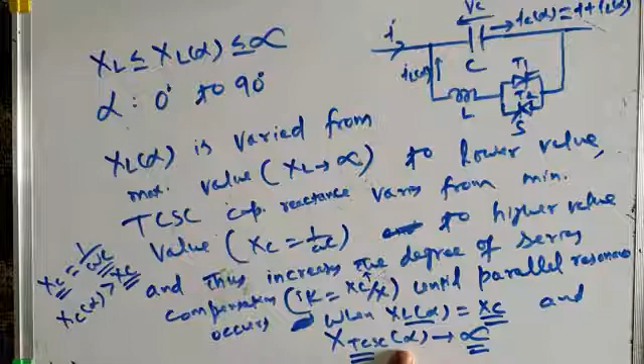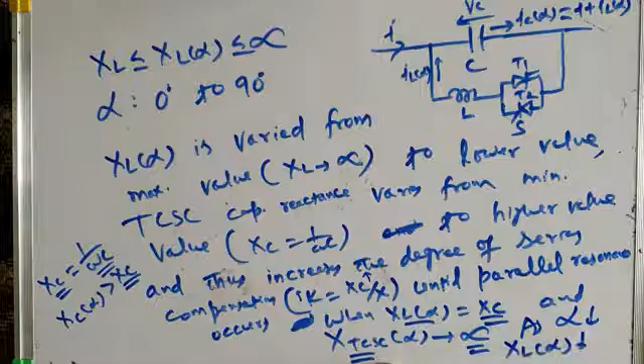And if we decrease alpha further, beyond where this parallel resonance occurs, it occurs at a particular value of alpha. It may be alpha equal to 40 degrees, 30 degrees, we don't know, for which XL alpha is equal to XC. As alpha is decreased further, what happens to the TCR reactance? TCR reactance XL alpha further decreases, and when it further decreases, overall TCSC reactance now becomes inductive. So earlier, up to the resonance, it was capacitive. Now the effective TCSC reactance, which is a function of alpha, becomes inductive in nature beyond resonance.